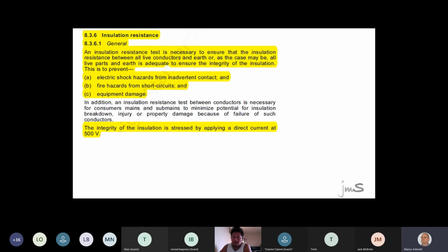Right, guys, so before I do the insulation resistance test, any test you do, if you don't test properly and you leave an installation live, can it kill someone? Can metal parts become live? Yes. Can it cause fire? Can it cause harm? Anyway, look at A, B, and C. The answer is there. It's in your 3000 book. The only thing which is not there is death. But you know that's the worst case scenario. Right, guys, now you're going to do the insulation resistance test. Why do we use 500 volts AC or DC?